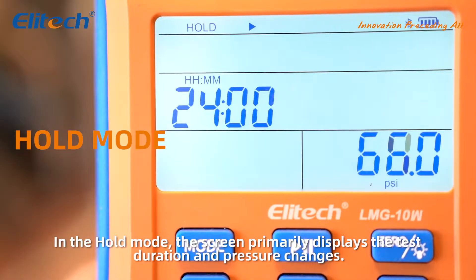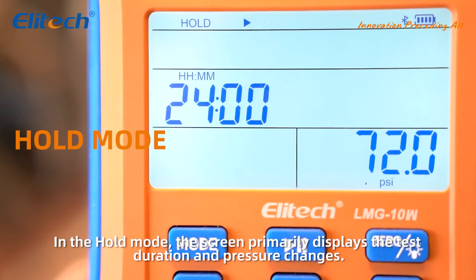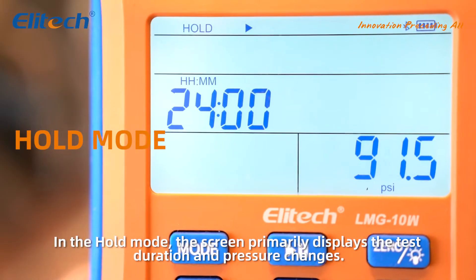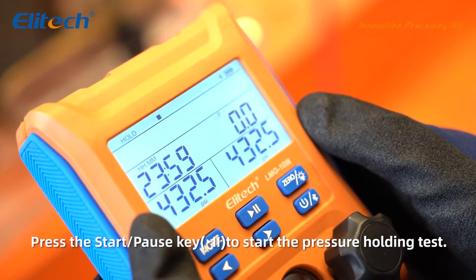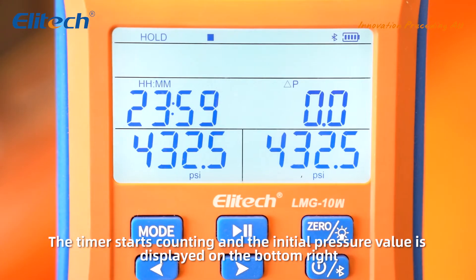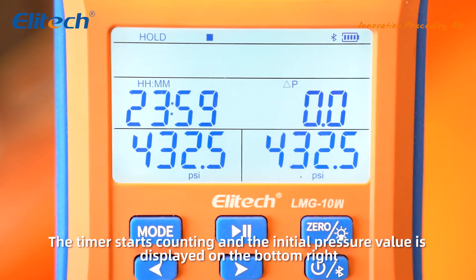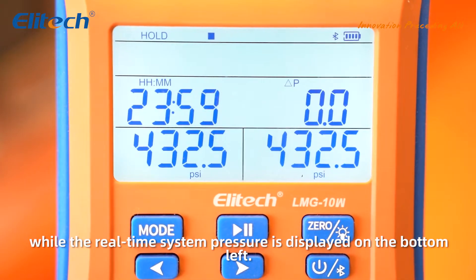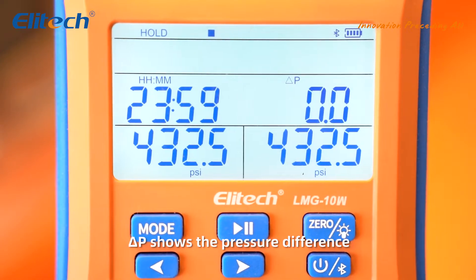In the hold mode, the screen primarily displays the test duration and pressure changes. The timer starts counting and the initial pressure value is displayed on the bottom right, while the real-time system pressure is displayed on the bottom left. ΔP shows the pressure difference.